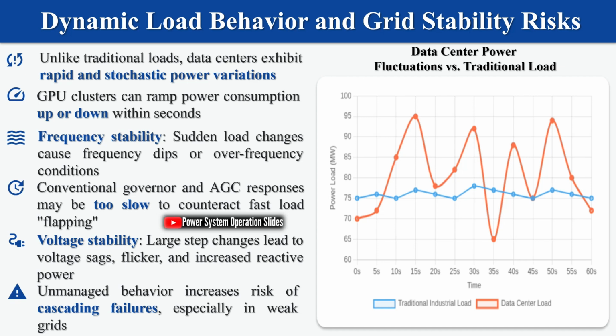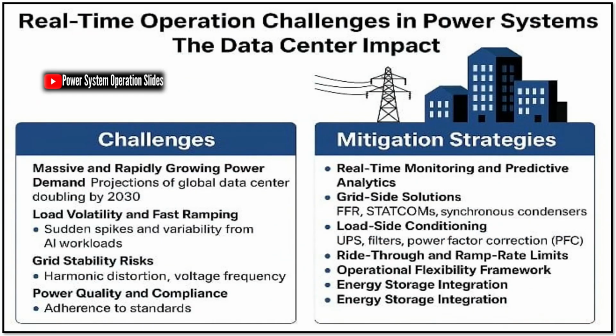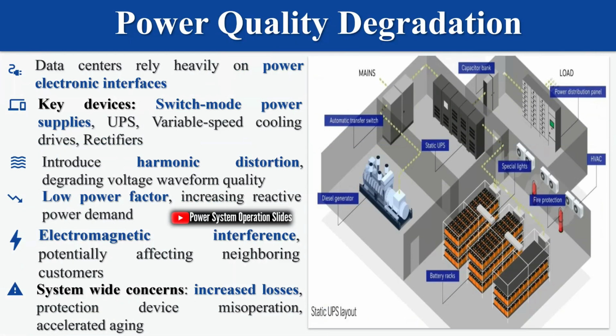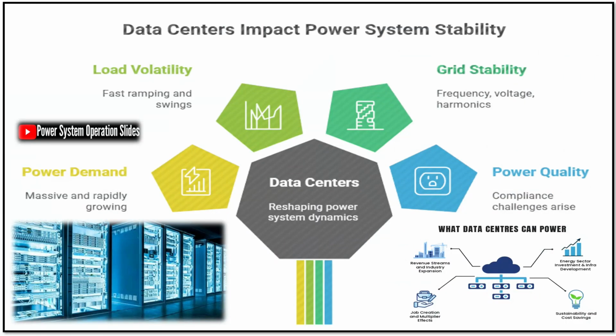Unlike traditional industrial loads, modern data centers, especially those supporting AI and machine learning workloads, exhibit rapid and stochastic power variations. GPU clusters and high-performance computing systems can ramp power consumption up or down within seconds, introducing challenges in frequency stability. Sudden load increases cause frequency dips, while abrupt load shedding can create overfrequency conditions. Conventional governor and AGC responses may be too slow to counteract these fast load flapping events. Similarly, large step changes in demand can lead to voltage sags, flicker, and increased reactive power requirements, threatening voltage stability.